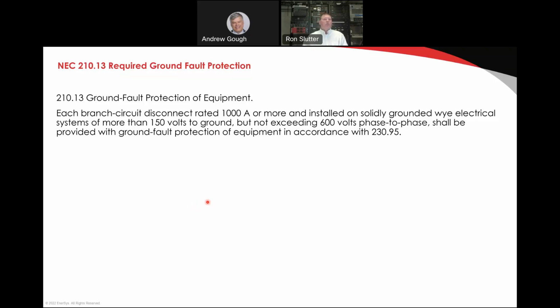When you get to those levels, let's take a look at 210.13. This is out of the 2020 NEC. It says each branch circuit disconnect rated 1,000 amps or more and installed in a solidly grounded Y electrical system of more than 150 volts to ground. So this is the key right here. A 480Y/277 volt system is more than 150 volts to ground. Because of that, code requires it to have ground fault protection. Once you get above 1,000 amps at 480Y/277 3-phase 4-wire, you need to provide ground fault protection on the main service equipment.